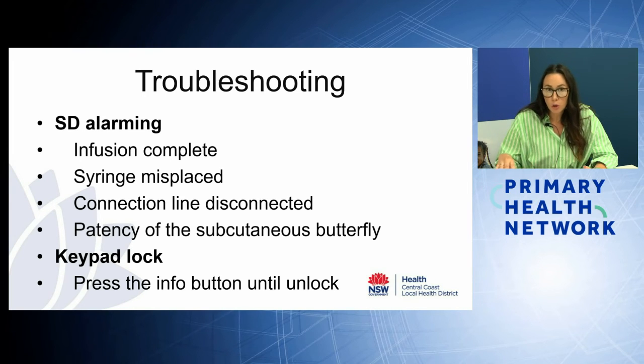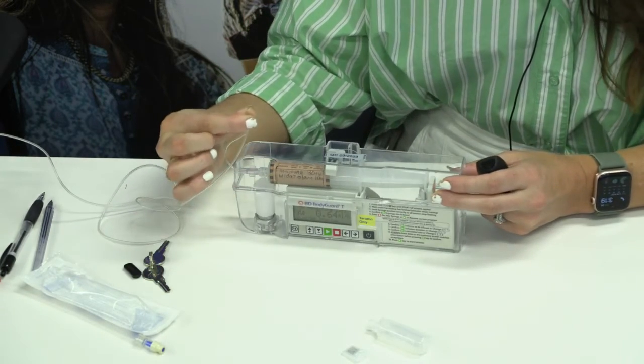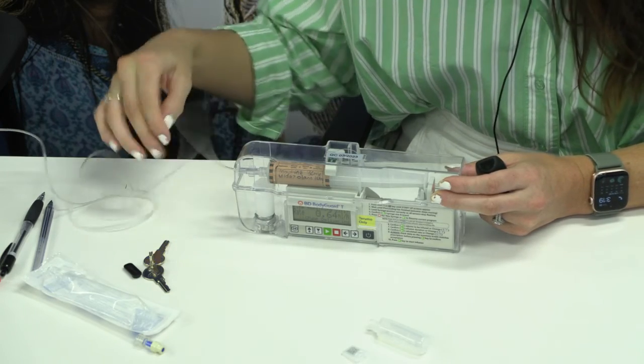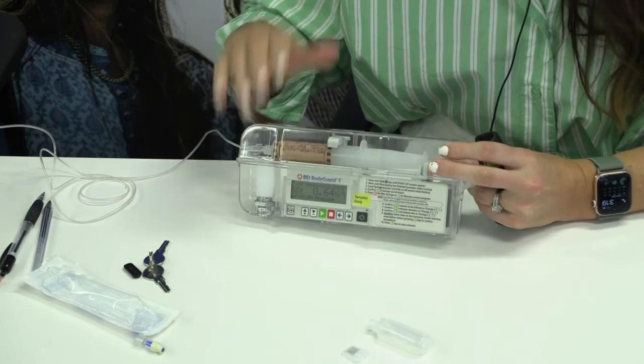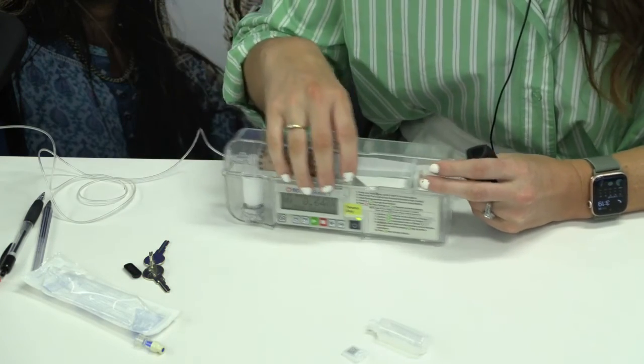So if there is an occlusion, it will come up on the screen saying line occluded. The machine is built for a particular pressure, so once it senses a particular amount of pressure, that sends an alert back to the machine to alarm. That can be as simple as a patient laying on the line being enough to completely occlude it. In most cases it's not. The majority of patients can lay on them and they are okay, but it's always best to try and remove it from the patient. But a total kinking of the line for a number of minutes will cause the machine to beep and alarm. So always check all of those things. Look at the screen first, see what the screen has to say, and then go from there.